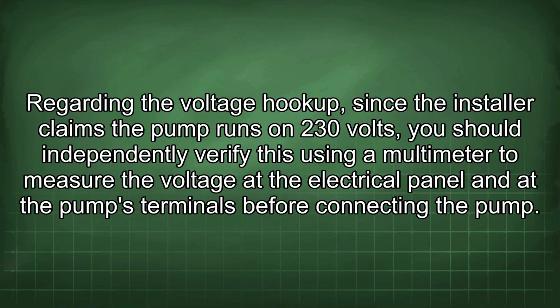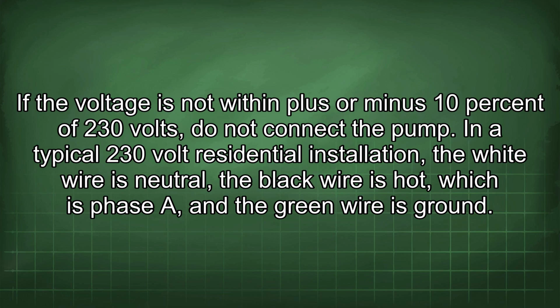Regarding the voltage hookup, since the installer claims the pump runs on 230 volts, you should independently verify this using a multimeter to measure the voltage at the electrical panel and at the pump's terminals before connecting the pump. If the voltage is not within plus or minus 10% of 230 volts, do not connect the pump.